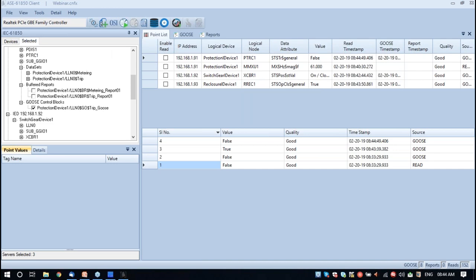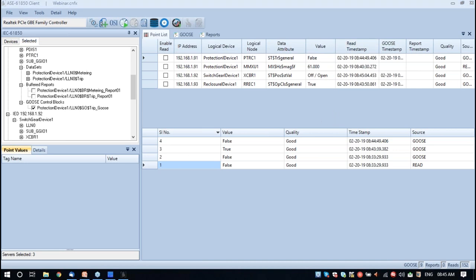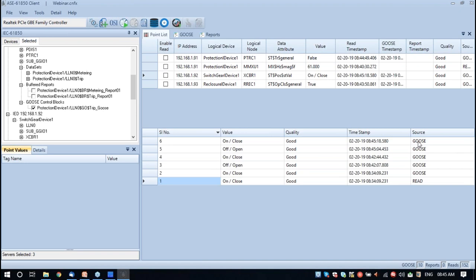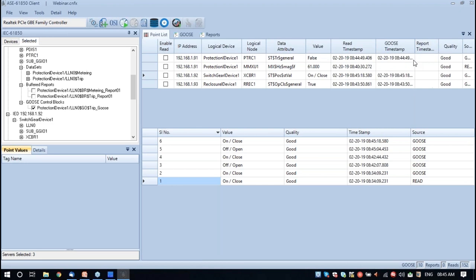If somebody wants to monitor a set of data points, that could be done very easily using this tool. It will keep on monitoring the signals and highlight those changes to the user. I will change the circuit breaker status. If you click on a specific data point, it will show the history and also the source of data retrieval, including quality and timestamp. Three timestamps are shown: read timestamp is updated whenever the tool reads the data, and GOOSE timestamp is updated whenever it receives the GOOSE signal. Measurement data is not transmitted through GOOSE, that's why you are not seeing a GOOSE timestamp there.